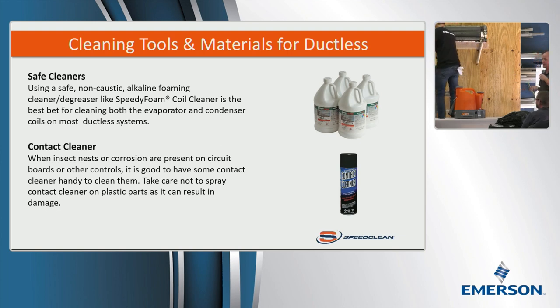Have some safe cleaners available to you. Don't just use the same cleaner for everything. If you're using the same cleaner for every application, you're doing it wrong. You need cleaners designed for tough applications, more heavily alkaline, for cleaning really dirty condensers, that sort of thing. And then cleaners for evaporator coils and conditions that are also going to be in the air the customer breathes. You don't want to use anything with strong odors when the customer could potentially breathe it.